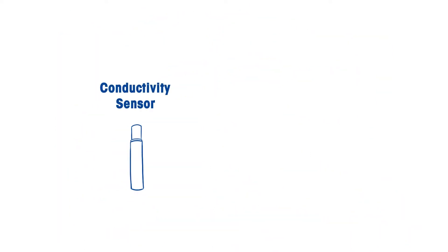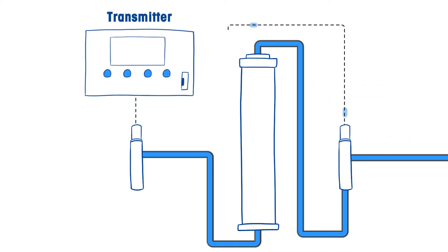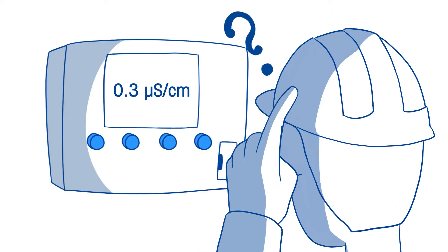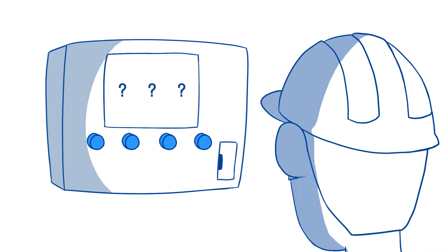As a cost-effective substitute for ppb-level measurement, plant chemists have relied on cation conductivity to monitor corrosion. However, while conductivity may provide an indication of change in corrosive conditions, it does not provide concentration levels of chloride and sulfate to ensure they are within acceptable limits.